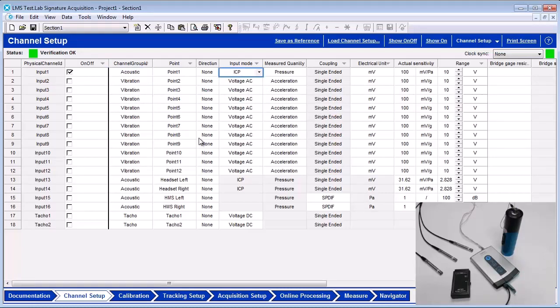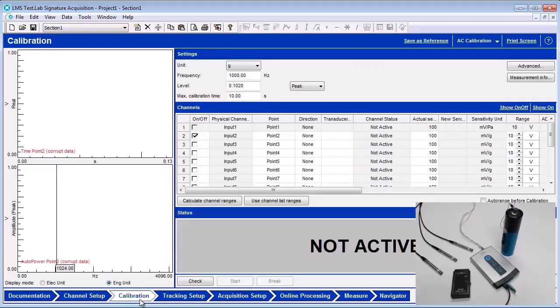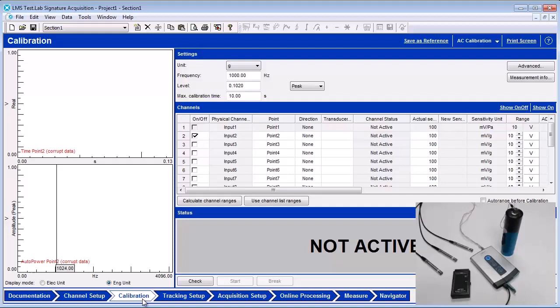In the calibration worksheet, enter the specific information for the calibrator being used. A microphone calibrator produces a specific frequency and amplitude level so the current sensitivity in millivolts per pascal can be calculated.